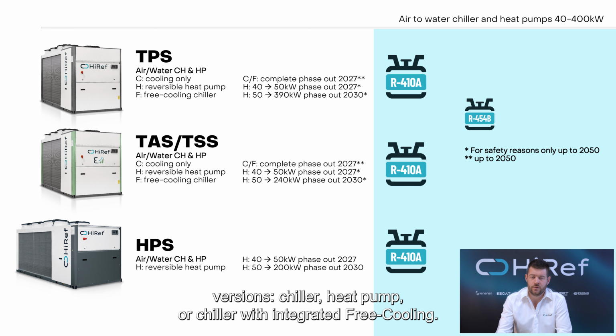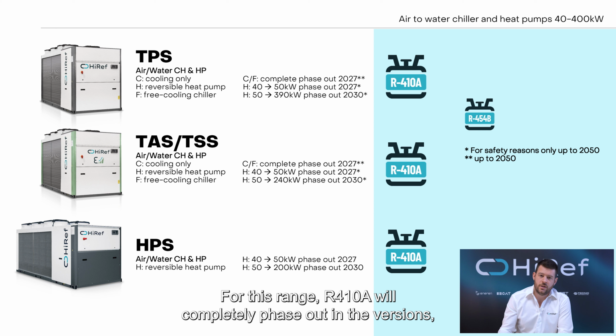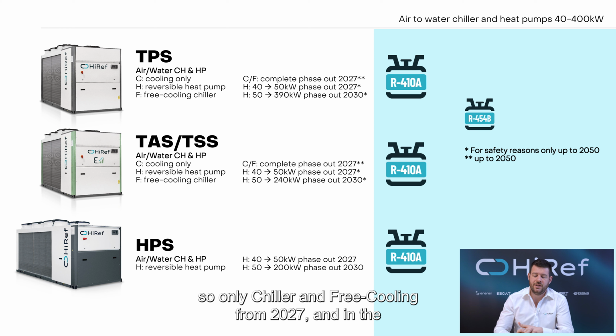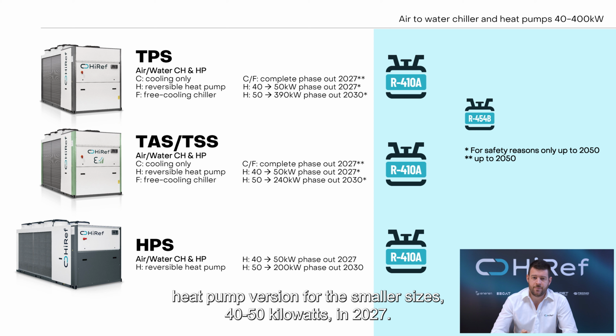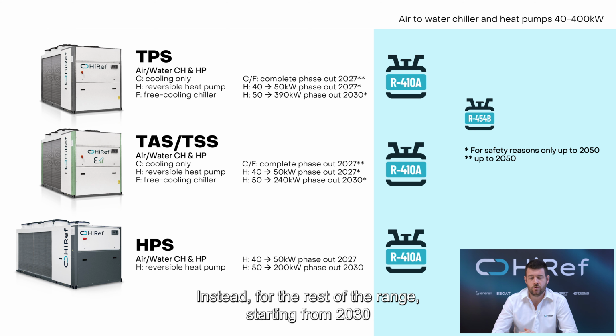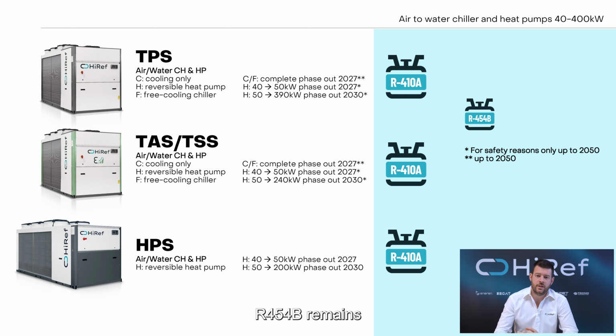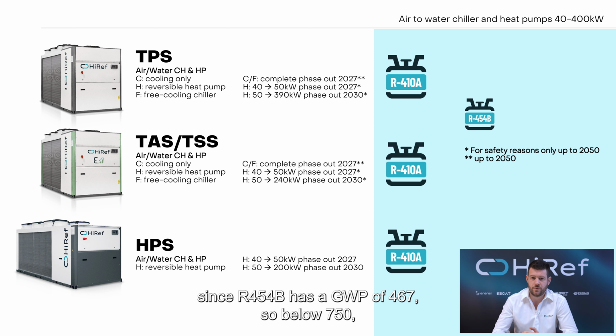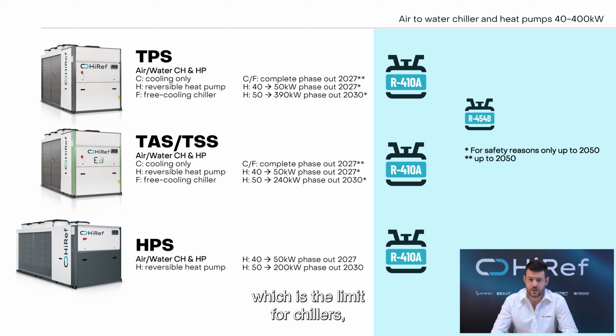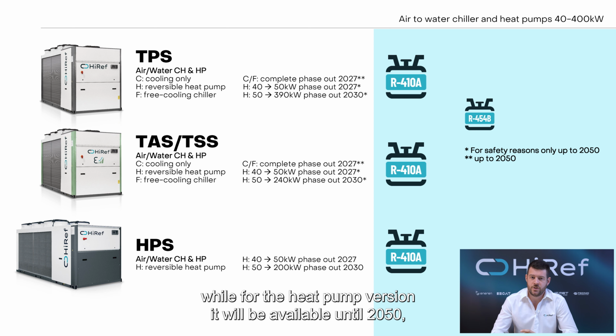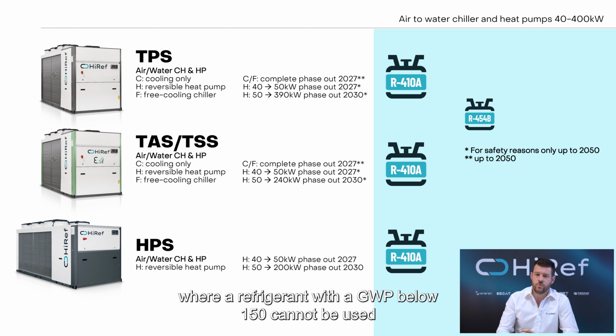For this range, R410A will be completely phased out in this version, so only chiller and free cooling from 2027, and the heat pump version for the smaller sizes, 40-50 kW, in 2027. Instead, for the rest of the range starting from 2030, R454B remains the valid alternative for this power range. For chillers and chillers with free cooling, it can be used until 2050, since R454B has a GWP of 467, so below 750, which is the limit for chillers, while for the heat pump version it will be available until 2050, but only for safety reasons, meaning only in the cases where a refrigerant with GWP below 150 cannot be used for safety reasons.